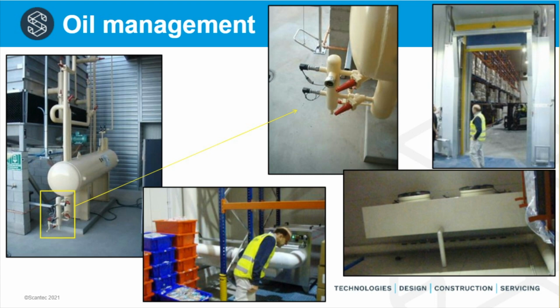The oil content in the refrigerant that is fed into the refrigeration plant is less than 1 part per million. It is not necessary to use this arrangement on all dry expansion ammonia plants. If one uses a compressor type that has low oil carryover, it's not necessary to do this. The cost can be reduced by not doing it.